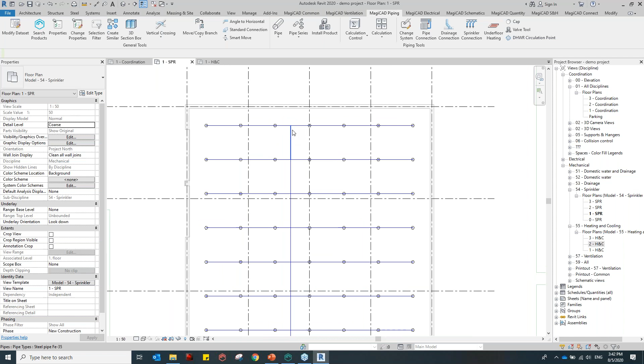Now next is how we do the sizing. When you want to do the sprinkler sizing, all you need to know is what sprinkler tables you want to use, especially when you look at our local standards, MS standards. MS standard says that end pipe must follow a different table. If you look at the MS standard, you will know what are the end pipe tables, what are the branch pipe tables, what are the main pipe tables already specified. You are already aware of it mostly.